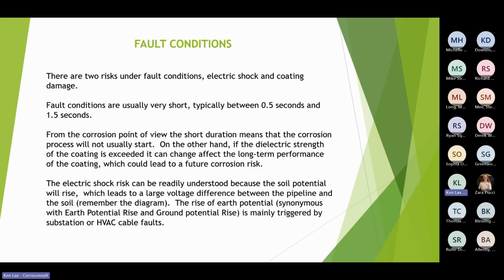We've got problems under fault conditions, which are electric shock and coating damage. The corrosion point of view, I explained a little earlier when we were talking about these sort of things. And we have to calculate the earth potential rise. You may find it referred to as EPR in the UK and much of Europe, GPR in the States as ground potential rise, and some people refer to it as ROEP, rise of earth potential. So we have to take into account those things as well.